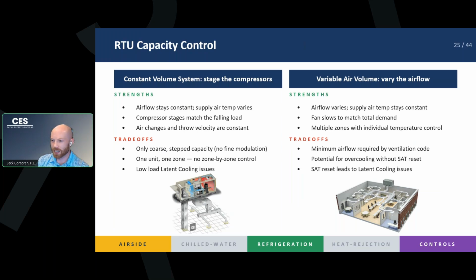Right on the left side, we showed earlier these two images at the bottom. The left side, you have one zone. We're going to dump constant volume of air. The CFM does not change, but we're going to vary the temperature of the supply air in order to meet our zone space temperature, right? There's only one thermostat. We're going to stage our compressors, right? Our compressors, like in VRF, slow down in order to meet the load.